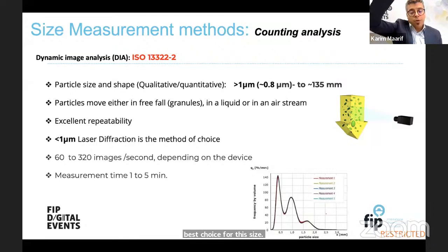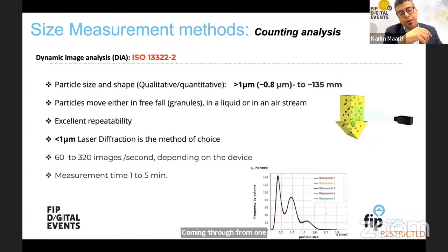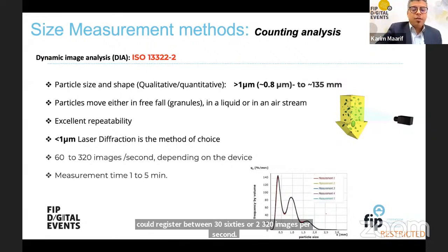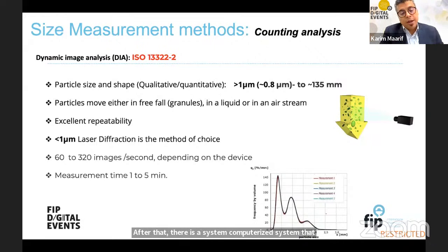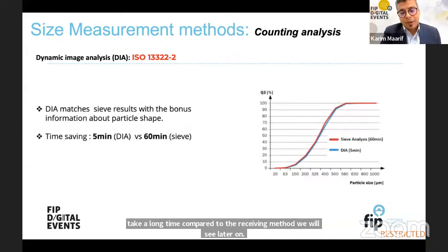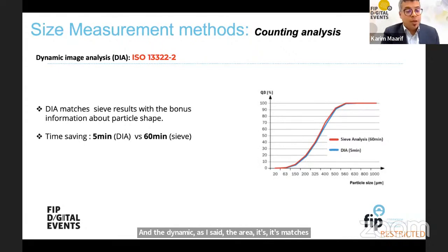In dynamic image analysis, when powder flows either by air, liquid, or gravity stream, a light source from one side records only the shadow of the particles on a screen. The camera can register between 60 to 320 images per second. A computerized system then analyzes the data and gives us an idea about the particle size distribution. Measurement time is between one to five minutes, much faster than the sieving method. Dynamic image analysis matches the sieve results with the bonus of providing information about particle shape in a shorter time.